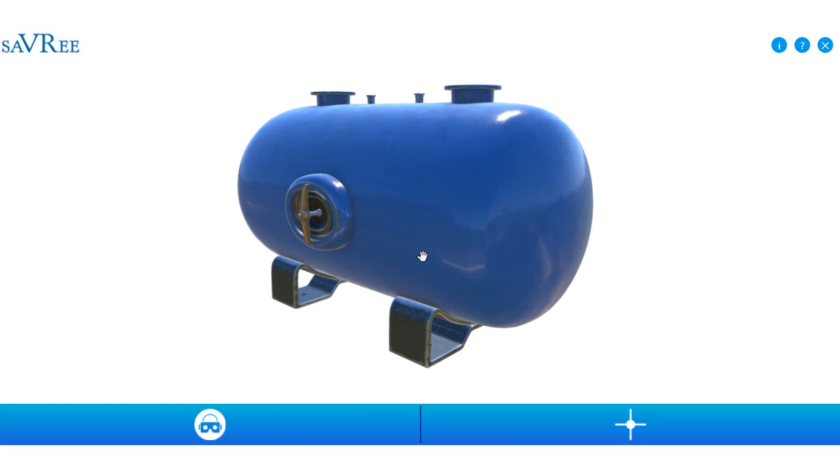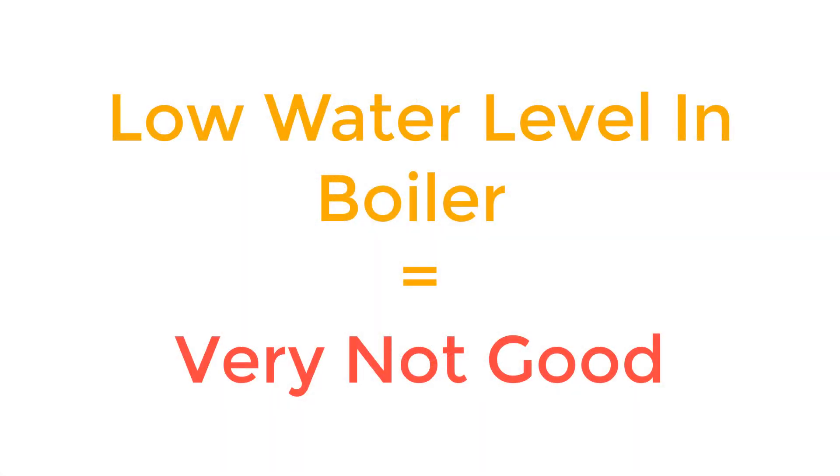You'll also see fusible plugs in older water tube and fire tube boilers. They were used in the past as a last resort should your boiler be low on water. So if the water level had gone so low that it uncovered the fusible plug, which was normally submerged in water.